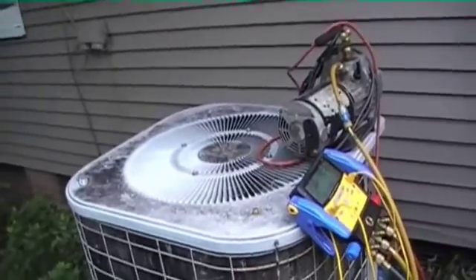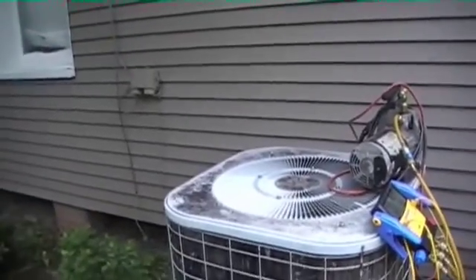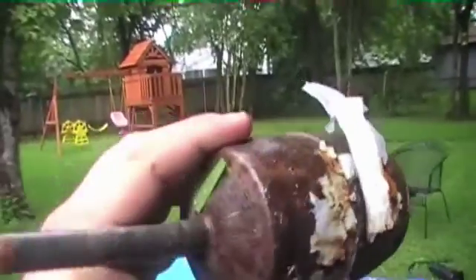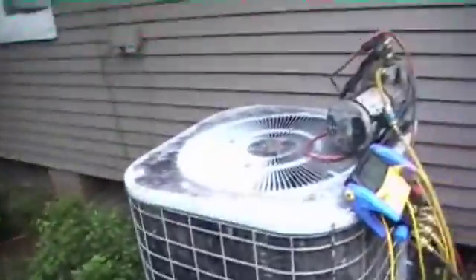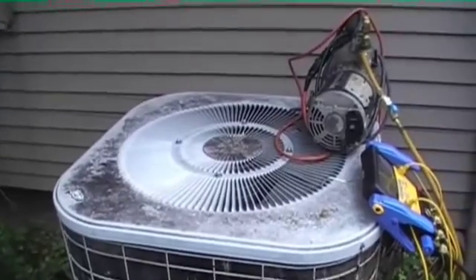It's coming down nicely — 700-something microns; 1000 is acceptable on R-22. I don't really trust the micron gauge on this machine, but I'm at 29 inches of vacuum. I did put a nitrogen pressure test on it and we held 150 pounds for about 30 minutes, which is a pretty good indication. I also replaced the old filter dryer — you can see that sucker was mighty rusty, getting ready to start leaking. Anytime you open up a system you want to change the filter dryer. We're gonna get this man cool and get this old Temp Star/Trane system back up and running.